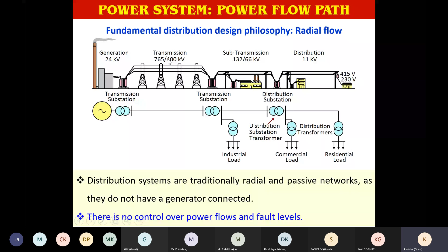Now a typical power system is designed as a radial system. That way you generate power at one location and extend power to a remotely located consumer. Power always flows in a particular direction. That is why we call it radial flow. But when you go for renewables, these are all distributed energy sources like wind farms and solar PV farms. Because the capacity is limited, normally small, may not be large megawatt level, especially a rooftop PV system where you are connecting to your 230 volt system. Or if it is a three-phase system, you are connecting it to a 400 or 415-volt system.